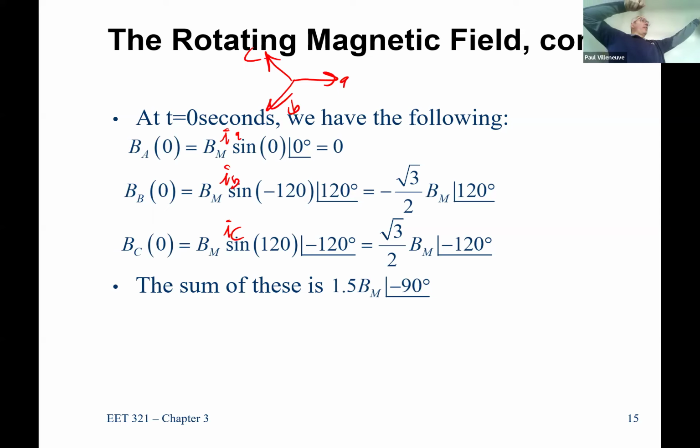Before, B was going into this part of the winding, and C was going over here. What we ended up doing is this: we reconnected the motor with our arms crossed, essentially.